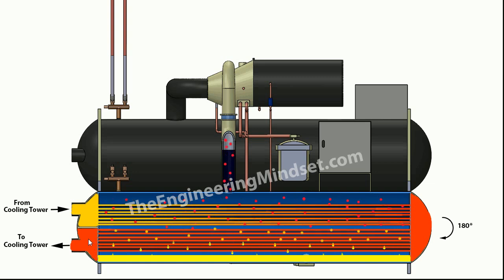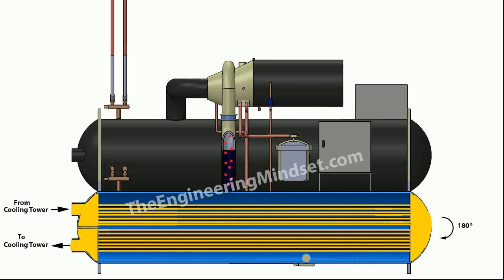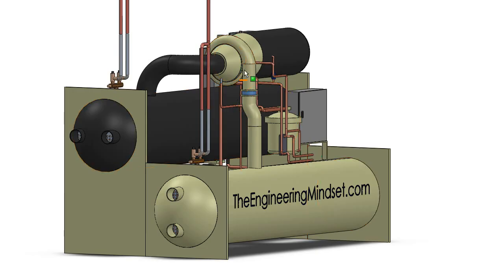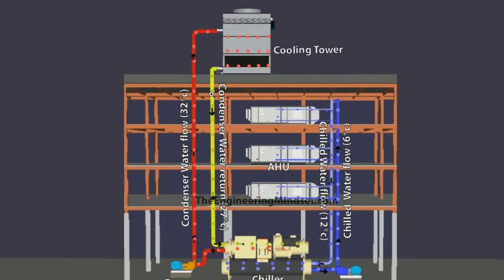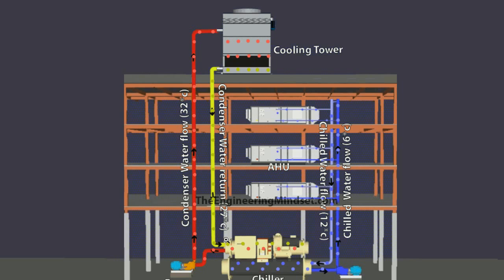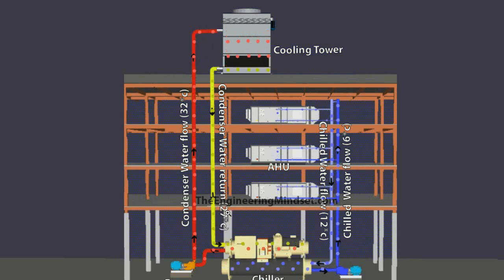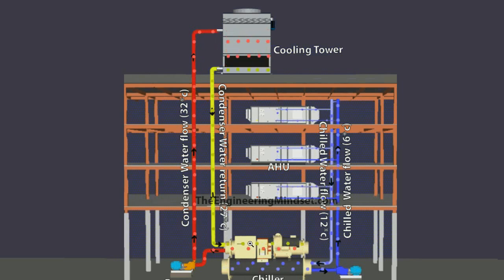Meanwhile, the hot condenser water heads off to the cooling tower. When the refrigerant exits the compressor and heads down towards the condenser through the discharge line, it needs to be at a much higher temperature than the return water coming back from the cooling tower — at 27 degrees Celsius or 81 degrees Fahrenheit. If the refrigerant coming out of the compressor is the same temperature as the return condenser water, your chiller will not be able to reject any heat from the building, and you will not be able to cool the building down.